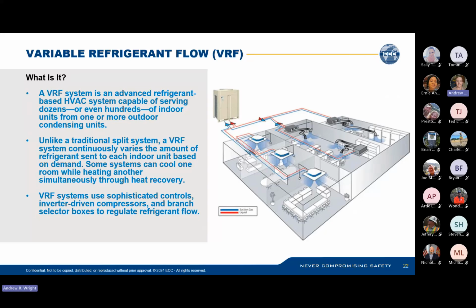So unlike traditional split systems, a VRF system continuously varies the amount of refrigerant sent to each indoor unit based on demand. So you could cool one room while heating another room simultaneously. It's a pretty sophisticated system that's very efficient. You'll see it in large office buildings or hospitals or other multi-occupied spaces like that. So it's something that you might come across. I know I've encountered it several times.